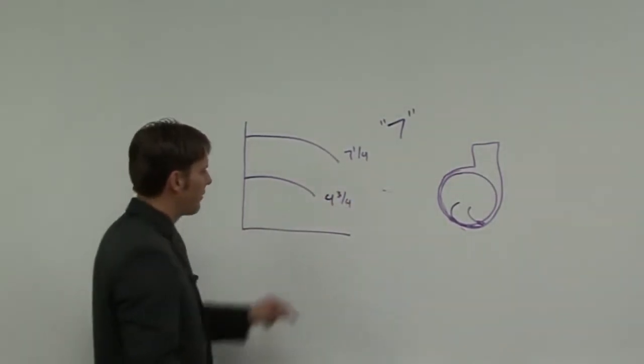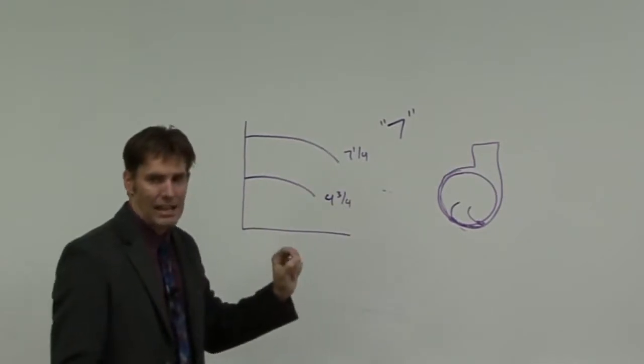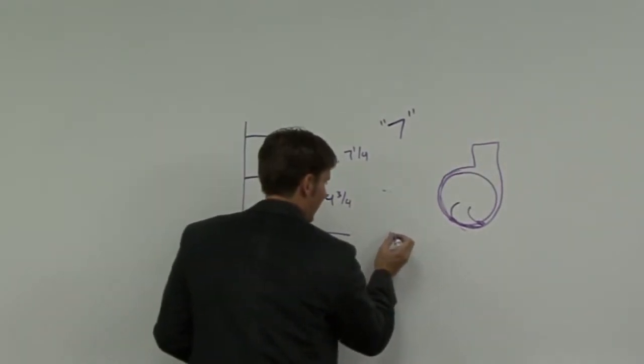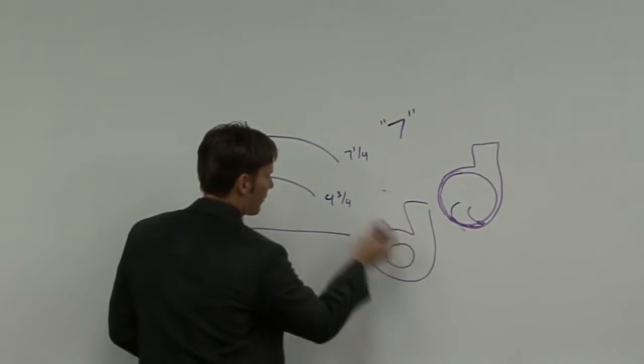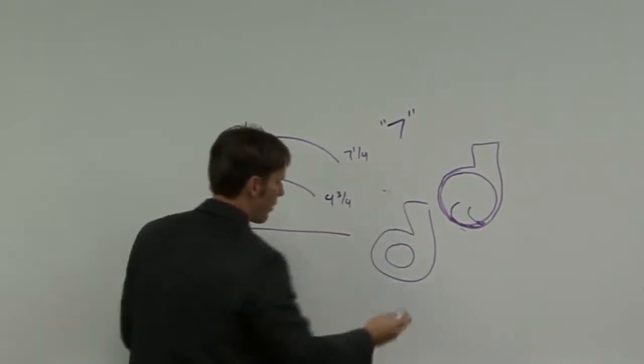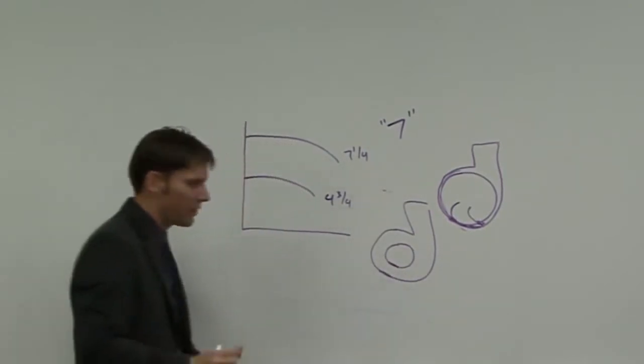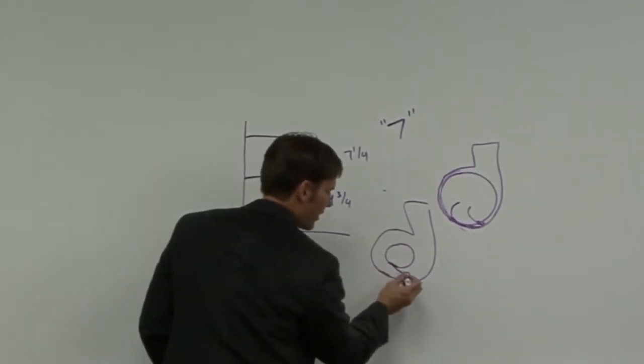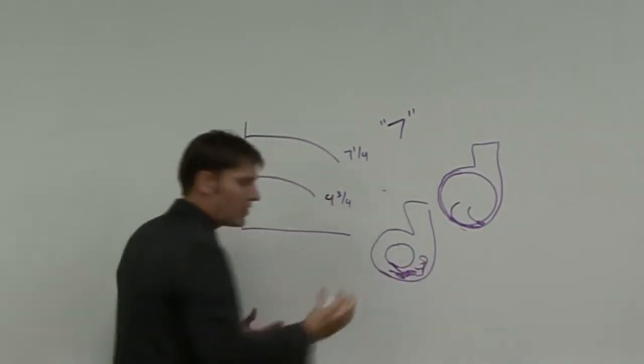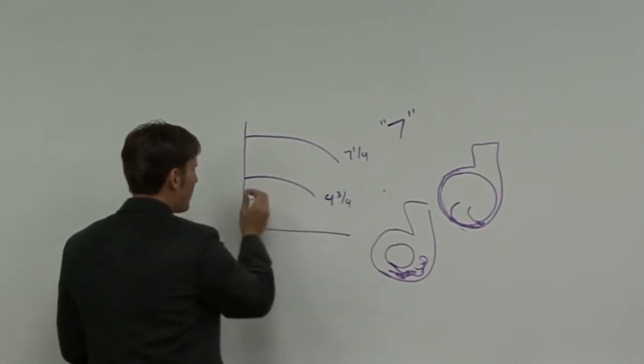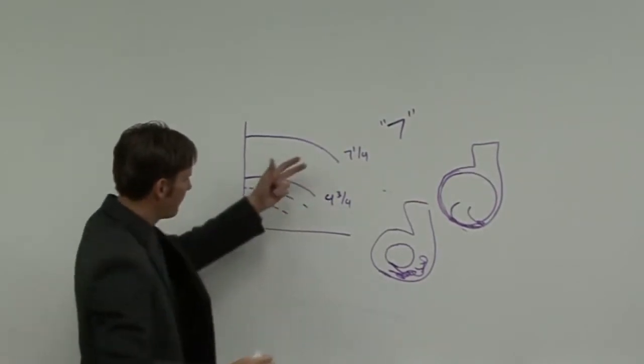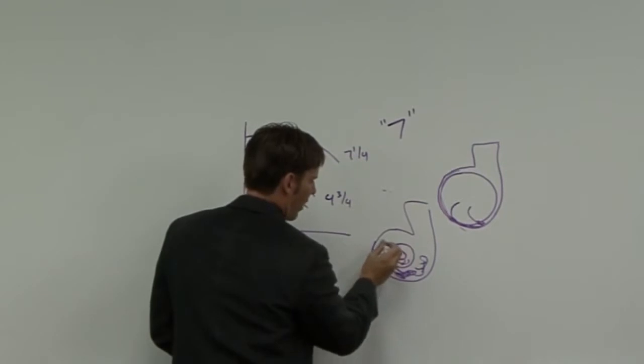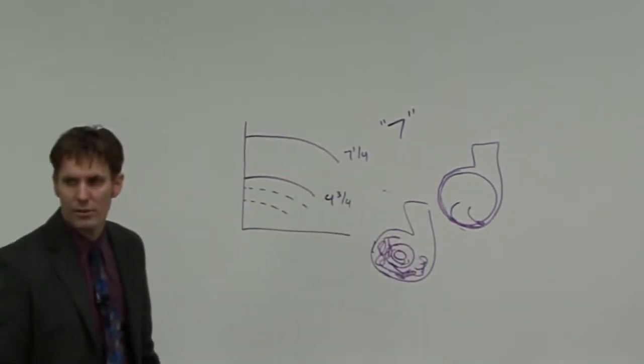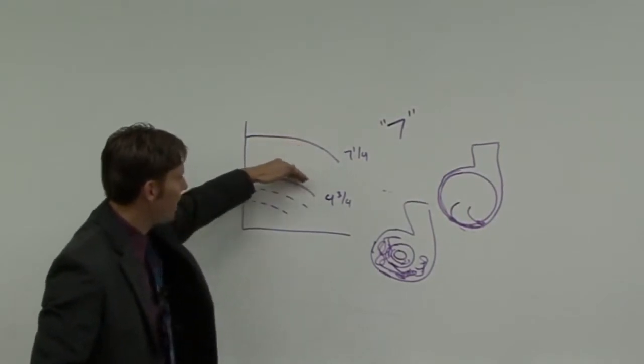On the other side of the curve, down here at 4 3/4, this is the smallest can, or the smallest impeller, I can put inside. So I take this same size volute, but now I've got a much smaller impeller. As I've trimmed the metal off of that, as I've made the diameter smaller and smaller, I've increased the gap size between these two walls so much that as my water spins out, it can turbulate around. And so the efficiency in my pump is going to decrease. If I keep going and assume that I can put smaller and smaller impellers in here, that distance becomes so great that it's rotating, but my water's just doing whatever it wants out here. It's not moving in the direction I want it to. That's why we have a maximum trim and a minimum trim.